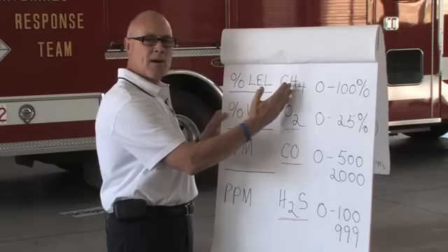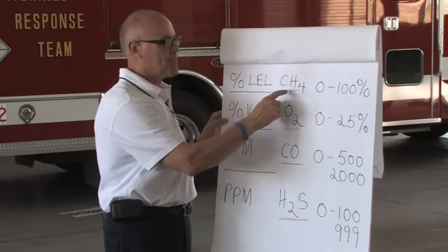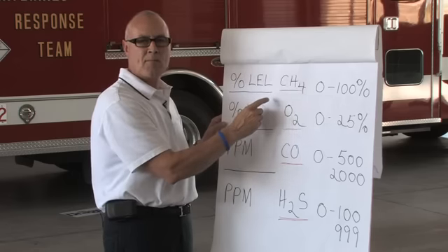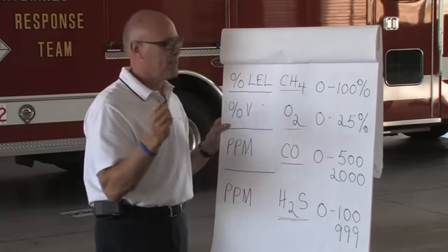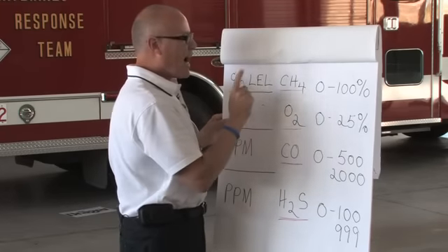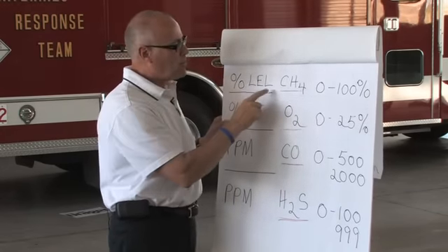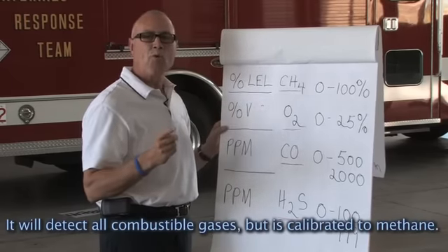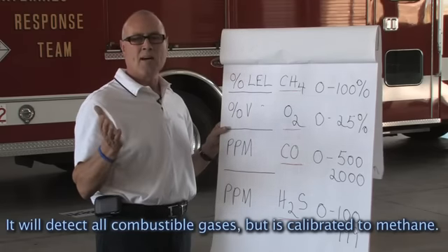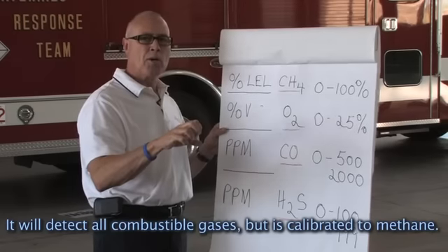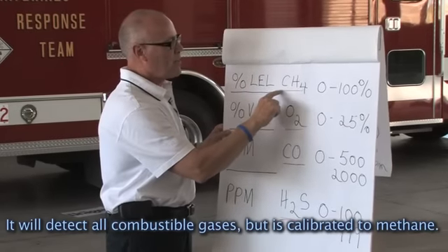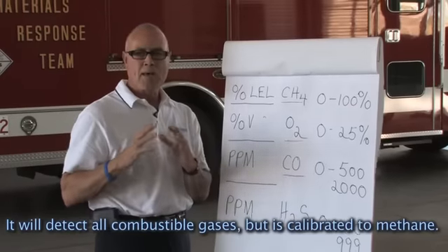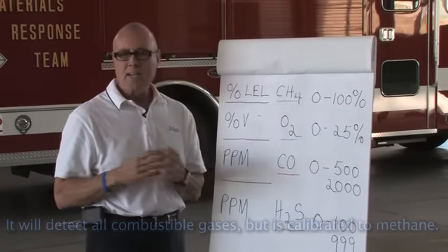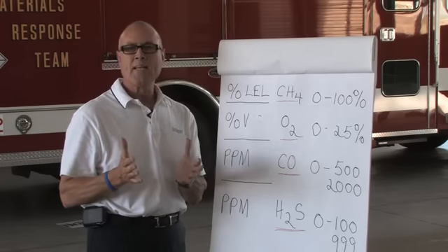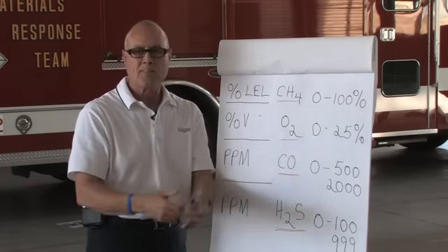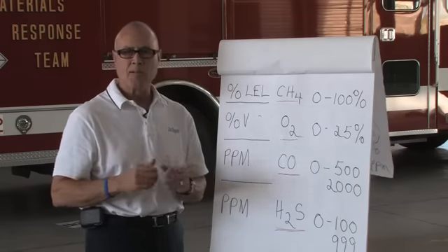So it has to safeguard you on the low end of the range because of different combustible gases that will be in the environment or could be in the environment. And remember, I've said it once, I'm going to say it another time, this scale, the hot wire sensor, the Wheatstone bridge, will burn any combustible gas that's present. It could be accumulative combustible gases or vapors, but they'll all burn on the sensor. It just happens to be that we calibrate it to methane, so that means if you're in a methane environment, the reading on your instrument should be a very accurate reading. If it says 23% of the LEL, you're in 23% of the LEL if you've got a good calibrated meter.